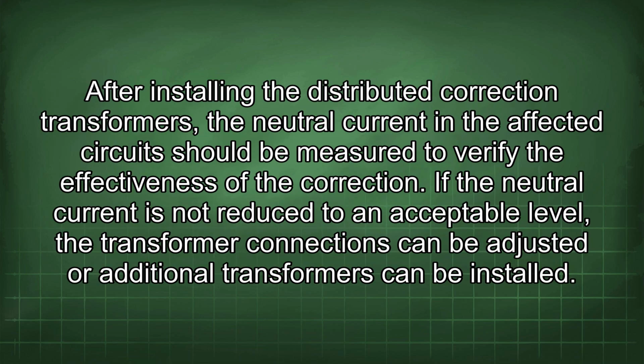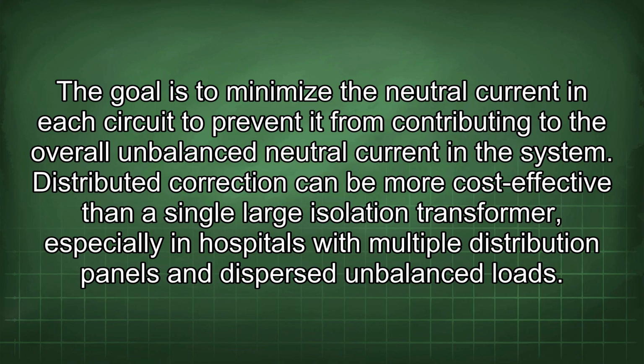After installing the distributed correction transformers, the neutral current in the affected circuit should be measured to verify the effectiveness of the correction. If the neutral current is not reduced to an acceptable level, the transformer connections can be adjusted or additional transformers can be installed. The goal is to minimize the neutral current in each circuit to prevent it from contributing to the overall unbalanced neutral current in the system.